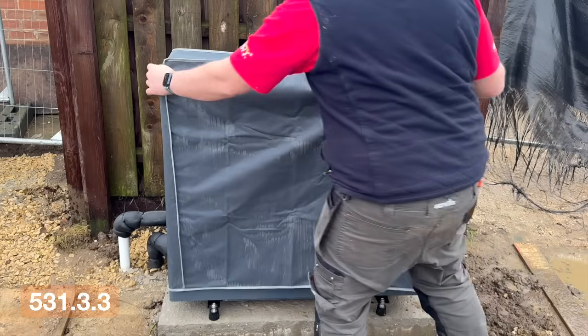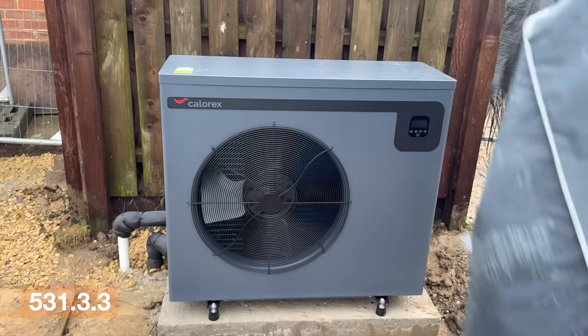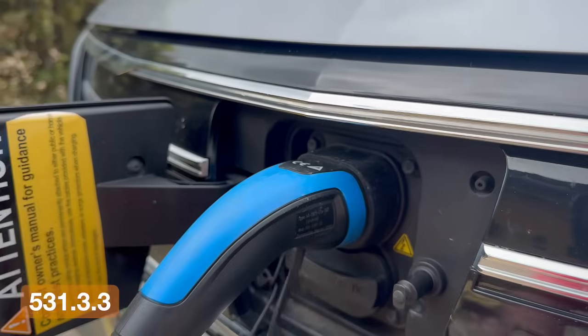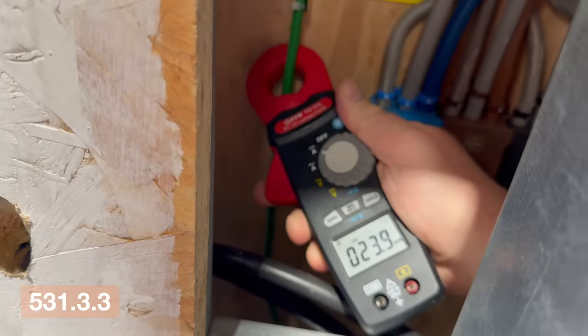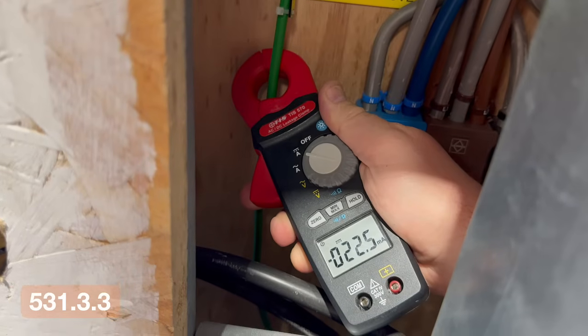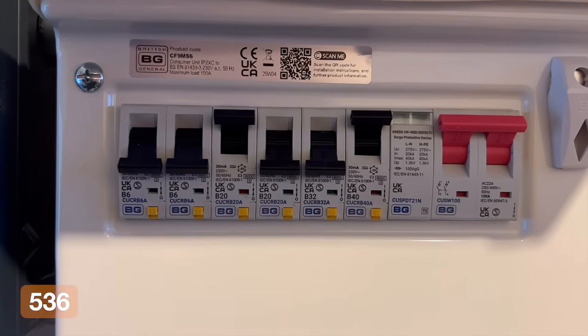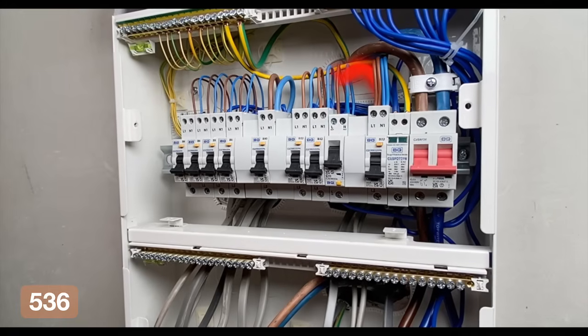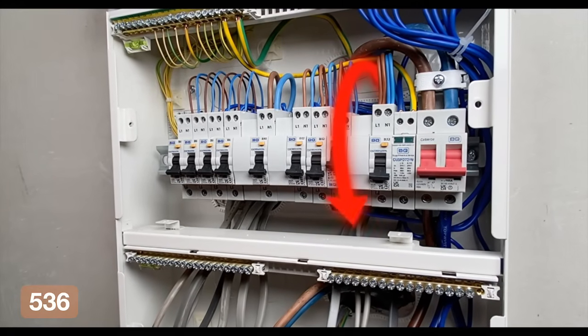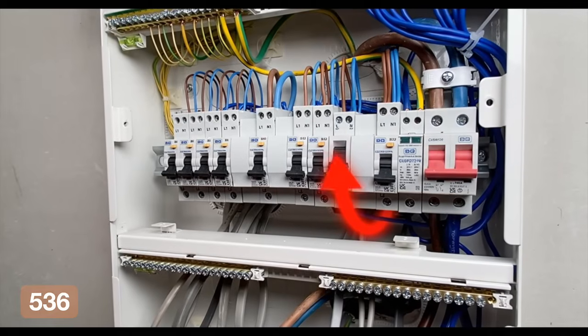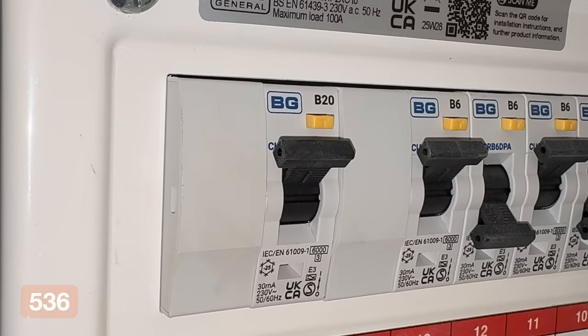This becomes critical when you start looking at systems with inverters, battery storage, EV charging, or anything with power electronics, because those systems can introduce DC leakage currents, and a standard type A device may not detect that properly, so it may not trip when it's supposed to. Section 536 has been redrafted to deal with how protective devices operate together. So selecting an RCD is no longer just about that one circuit, it has to work as part of the overall protection strategy for the installation, which means thinking about upstream and downstream devices, selectivity, and how the system behaves under fault conditions. So what does this mean, and how should selectivity look when it comes to RCD types?